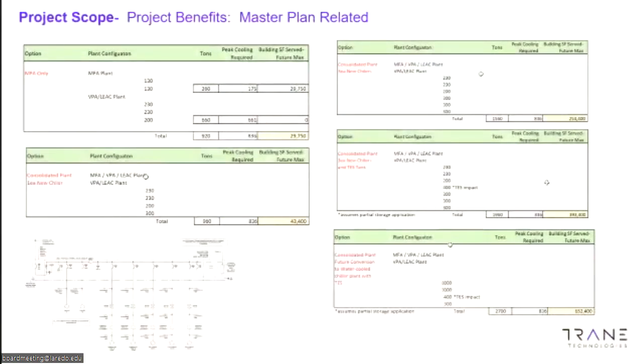Just to make the point here: what you see in the upper left is if we were to just replace the chillers at the MFA building without consolidating, you'd have the ability to add roughly 29,000 square feet of extra space. If we consolidate the plants and only add one 300-ton chiller, the electrical infrastructure will accommodate up to 3 additional 300-ton chillers. But if you just did what we're advocating today, you could add another 10,000 square feet to these two plants.